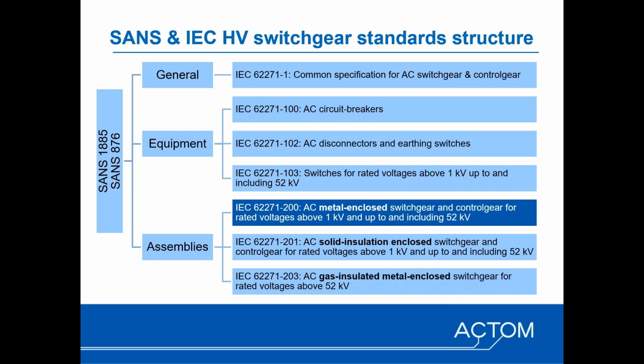Briefly, just by way of a very high-level overview, this is certainly not exhaustive, but just an overview of the SANS and the IEC high voltage switchgear standards and the structure. We've got on the right-hand side the different IEC standards. So for example, one of the most common would be 62271-1, which covers all the common specifications for AC switchgear and control gear. -5 is about to be published, which covers the common requirements for DC switchgear. A lot of work going on at the moment for high voltage DC switchgear in the relevant IEC technical committees 17, 17A and 17C.